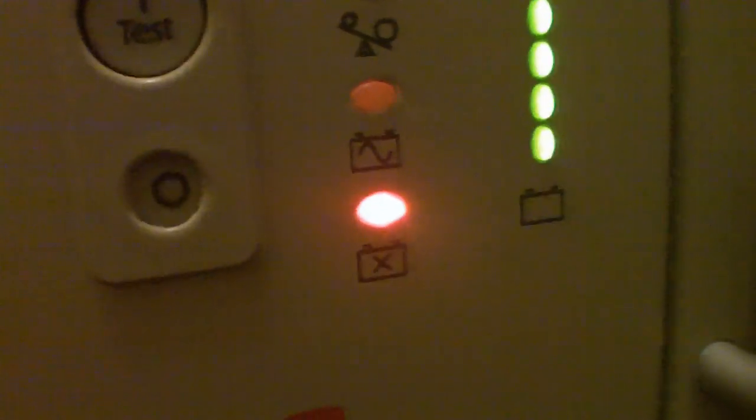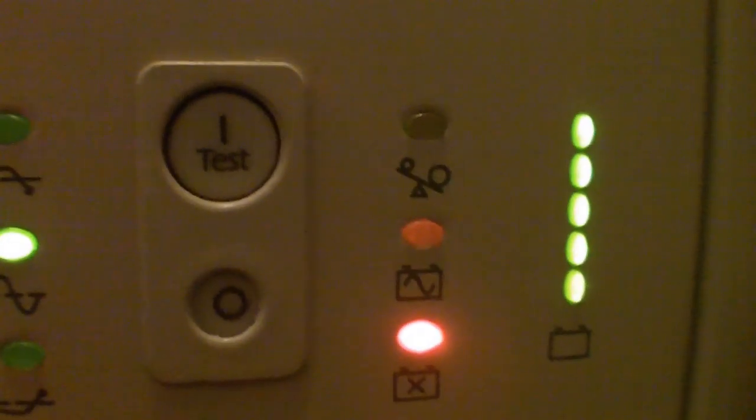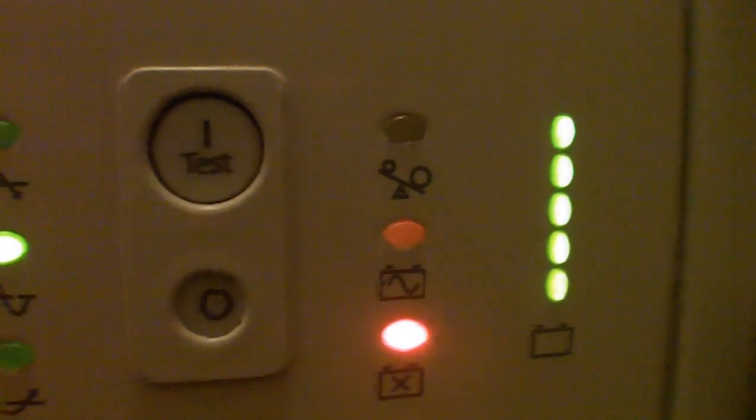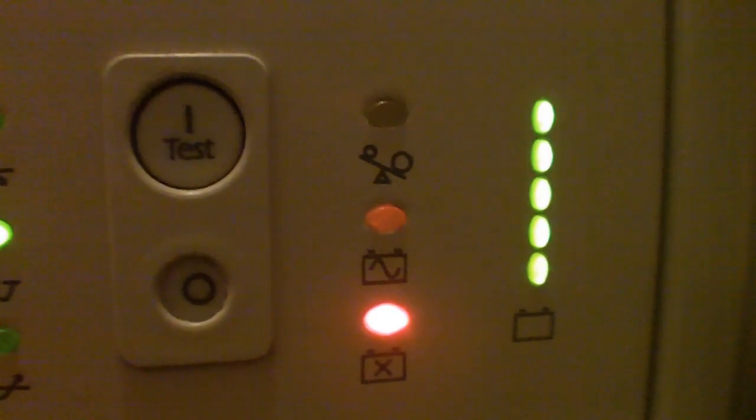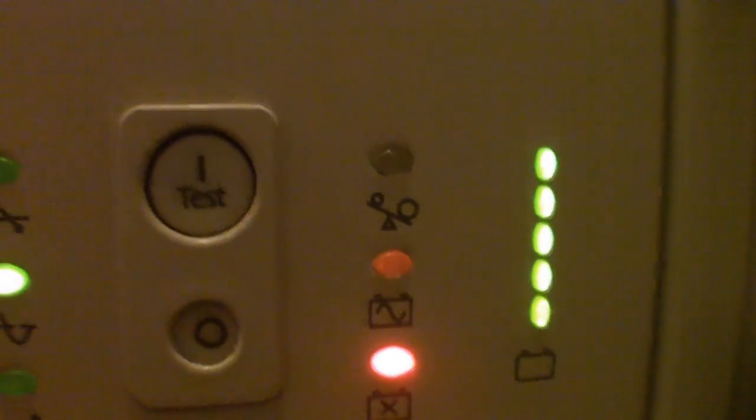So what are the signs you need to replace your batteries? Well, that nagging red light on the front next to the battery indicator is one sign. Another was when all of our equipment hooked up to this unit shut off when the unit runs the auto test once a week. That's definitely a sign that we noticed.